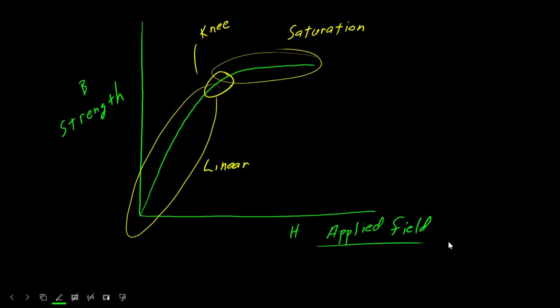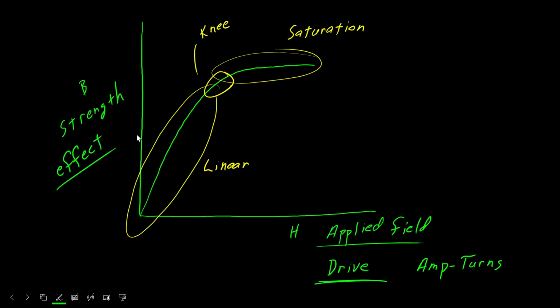Let's go back and consider this applied field. You could think of this as the drive signal. Technically it's the amp turns, but for our purposes this is roughly equivalent to the voltage. So we have the drive, and then we have the effect. You may attempt to establish a magnetic field in that transformer, and this shows what that magnetic field is. This is fine in the linear part because there will be a linear relationship between cause and effect, right up to the point where we have this knee.